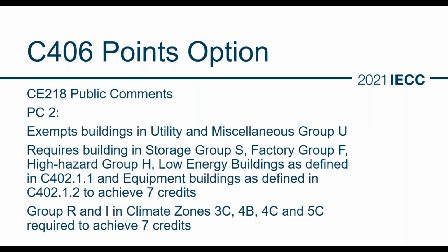Public comment 2: we realized that these options also apply to low energy use buildings. The current format in the 2018 also applies to low energy use buildings, but the modification of the format actually had an unintended consequence, is probably the best way to describe it, on how this would apply to these buildings. And so some of the buildings were exempted. Utility and miscellaneous Group U, for example, are exempted because it doesn't make sense to add these additional efficiencies there. The number of credits was reduced to 7 credits for Group S, factory Group F, high hazard Group H, low energy use buildings as defined in C402.1.1, and equipment buildings, because again, right now in the 2018, the packages apply. So this was reduced to 7 credits just to make it more realistic.